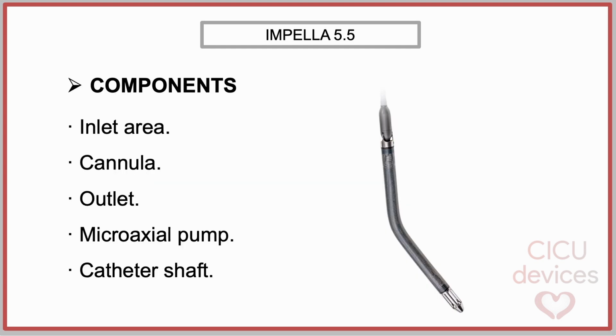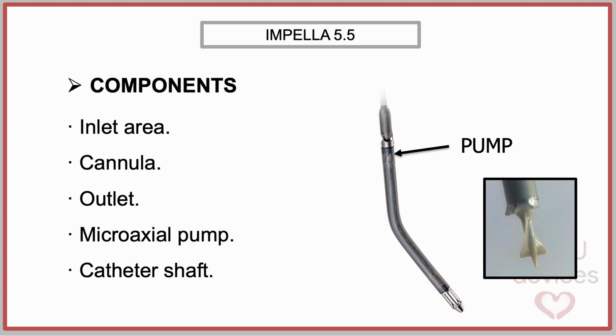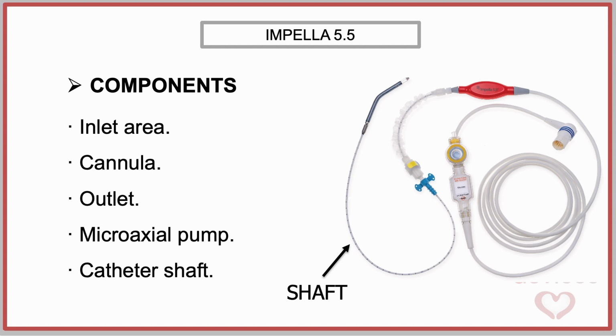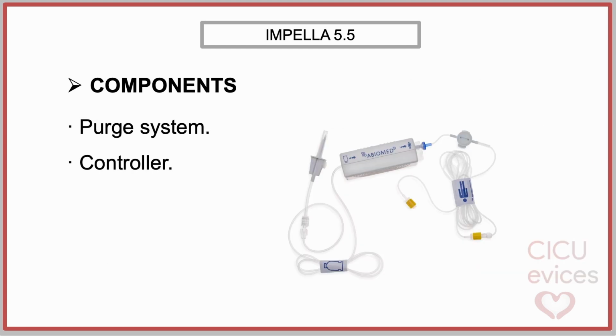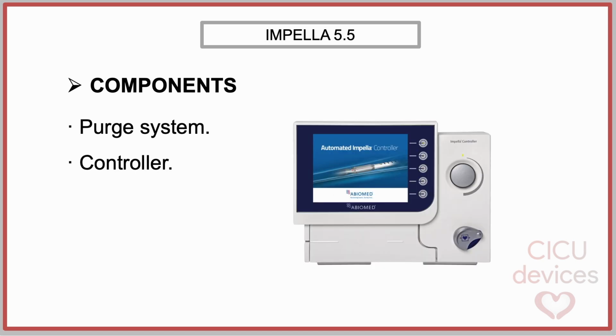The Impella 5.5 consists of several structural components. The inlet area, positioned within the left ventricle, which aspirates blood. The cannula, a plastic conduit that facilitates blood transport from the inlet area to the outlet. The outlet area, positioned in the ascending aorta, which expels blood. The microaxial pump impeller. The catheter shaft, that contains the motor drive cable, the fiber optic pressure sensor line, and the purge line. The purge system delivering heparinized solution to prevent blood entry into the motor housing. And the external automated Impella controller, which regulates pump performance and displays hemodynamic parameters.